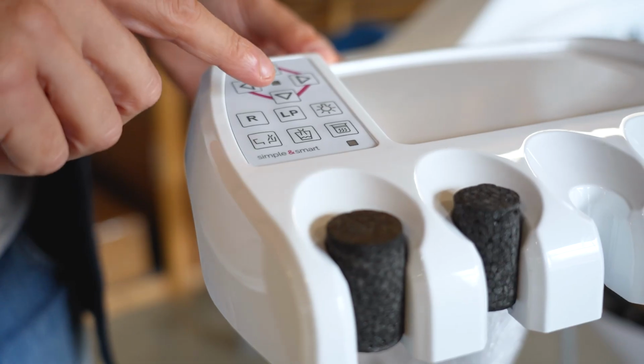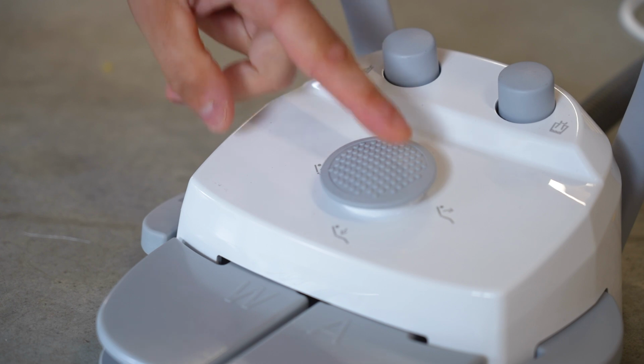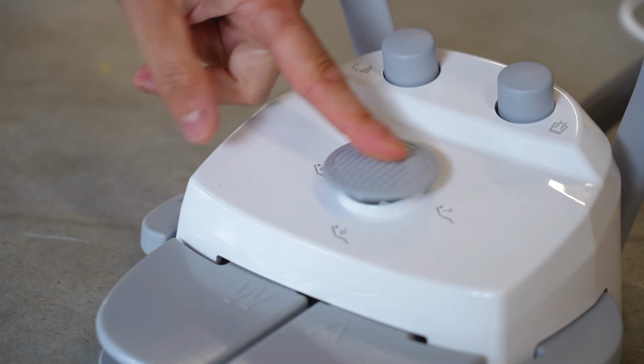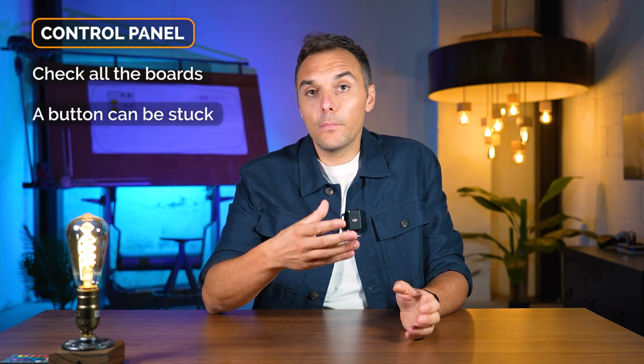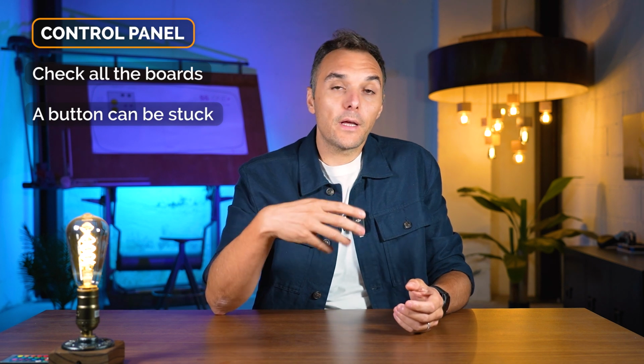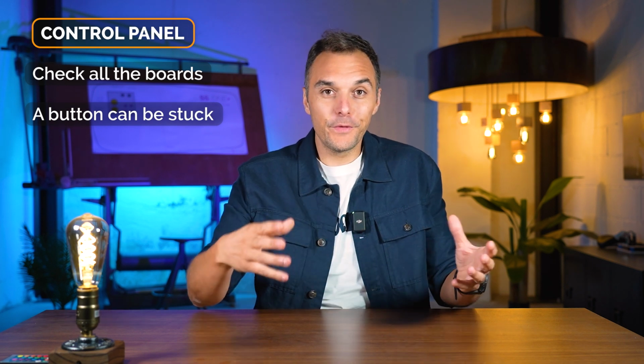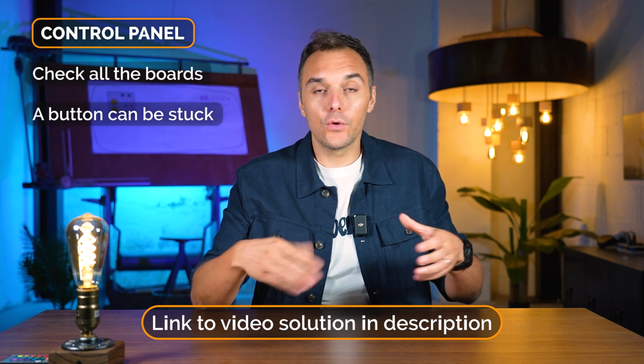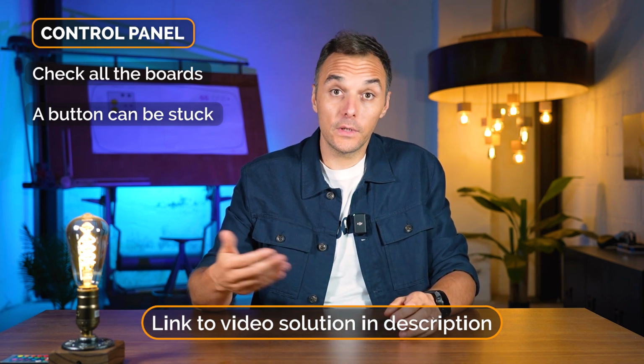The fourth thing that can cause the chair to not move correctly, or some other issue, can be related to the control panel that we have on different parts of the chair. It can be the control panel of the doctor tray, the assistant tray, or the pedal, if you have the switch on the pedal or on the back of the chair. If one of these is damaged or has some issue, like a button that cannot be pressed correctly, it can be the cause of the problem. If one button is pressed, this can be the cause of the chair not moving, because you cannot touch other buttons around, or it can give some malfunction on the dental chair in general.